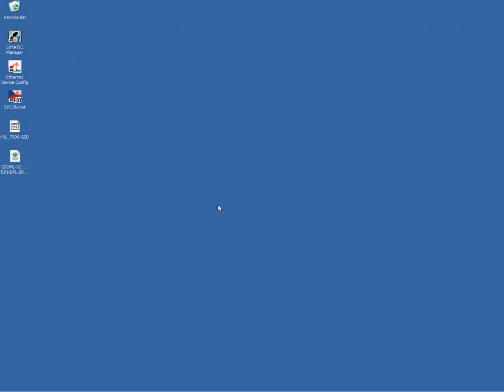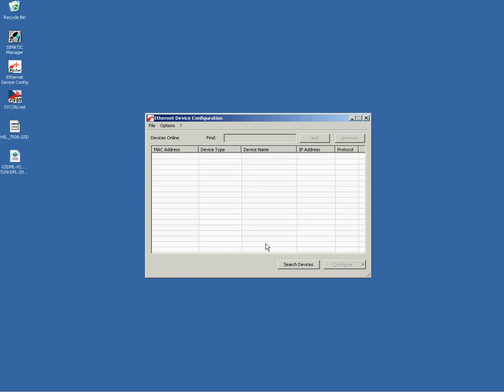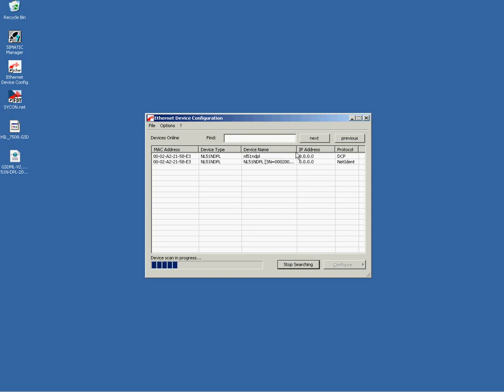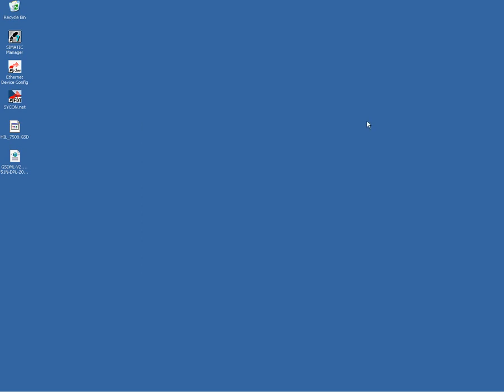Before we configure the Profinet IO controller, I just want to show you something. Since we set up the IP address temporarily and made a download via Sycon configuration software, you see that Netlink falls back to the IP address zero. This is expected since the Profinet IO controller will give it later on its real IP address.